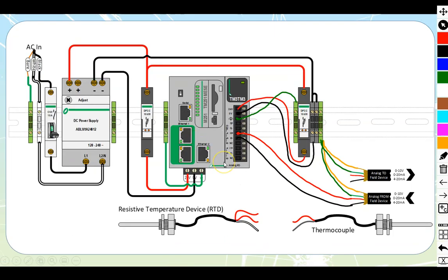Straightforward as well. The last one that we're going to take a look at would be using these things for temperature sensing. So we've got a thermocouple and we've got an RTD. If I've got a thermocouple, it's going to be two wire, and I just need to take it to the plus minus. So we'll do that over here. Take this one up and into my plus, we'll take this negative from my thermocouple up and into my negative like that. That's my thermocouple wiring. If it was a shielded cable coming in from there, which it should be, you would also be tying that down here. I'm just showing the actual threaded-in thermocouples themselves.